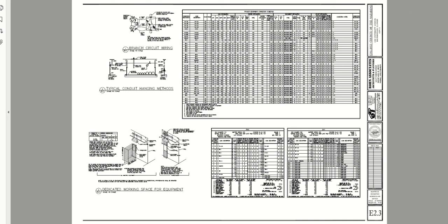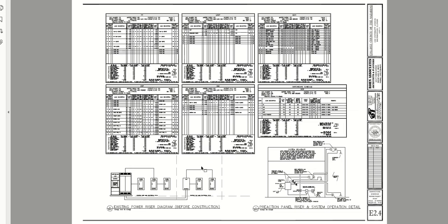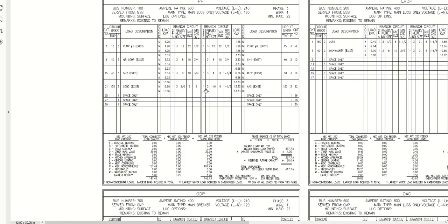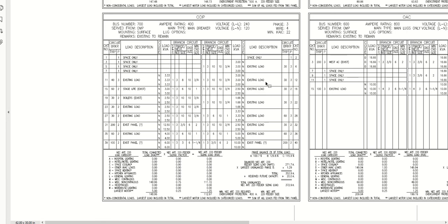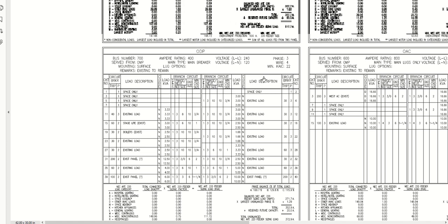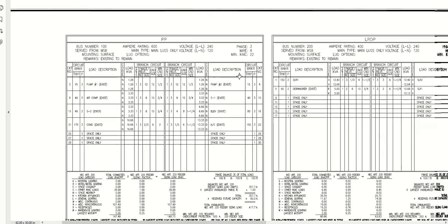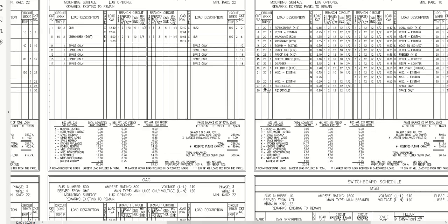There's also some power diagrams showing conduit hanging and space requirements. We included a couple of panels here, making use of the space. This is done many times on existing plans—we're showing the existing panels before construction. We do this to set a baseline to show how much load they're using and to justify the load that we're adding. This is the existing power riser diagram showing what was there before we started, and these are the panel schedules for those panels showing the existing load.